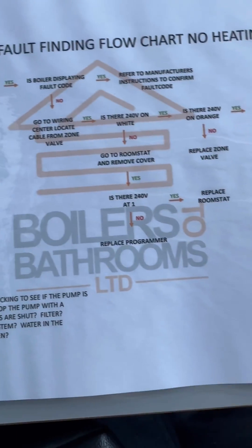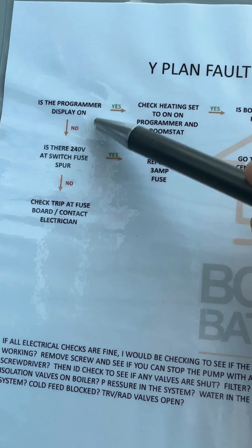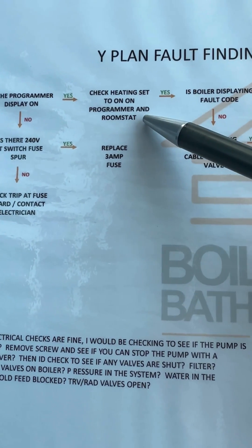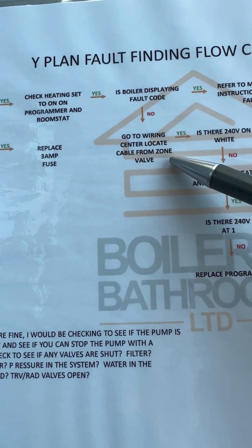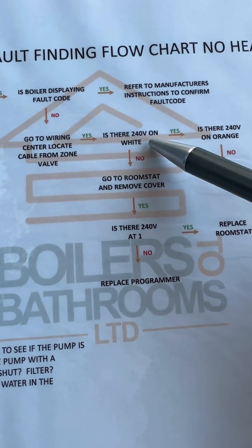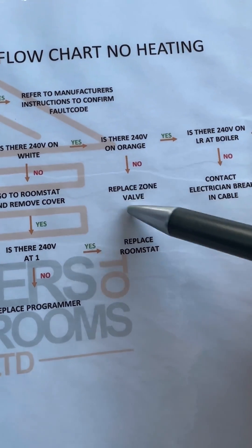Y-plan fault-finding flow chart: no heating — is the programmer display on? Yes. Check heat set to on on the programmer and the room stat — yes it was. Was the boiler displaying a fault code? No it wasn't. Go to the wiring center, locate the cable from the zone valve — is there 240 on white? Yes. Is there 240 on orange? No. So replace the zone valve.